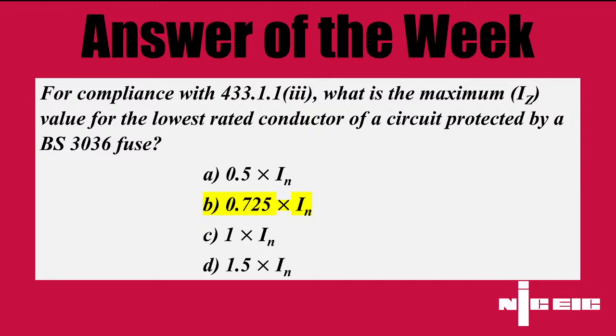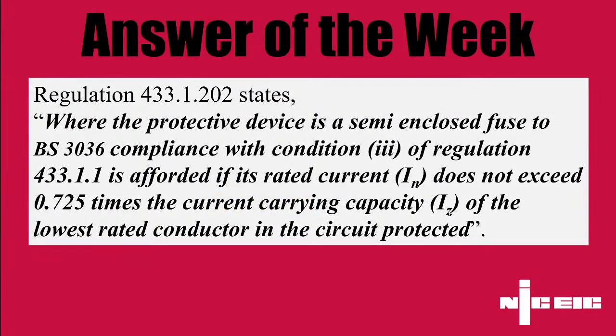If we go through a little bit of information as to why that is, within BS 7671 itself, firstly we'd be driven by Reg 433.1.202, which says where our protective device is a semi-enclosed fuse to BS 3036, then in order to meet indent 3 of regulation 433.1.1, it's afforded if the rated current does not exceed 0.725 times the current carrying capacity of the cable, Iz, of the lowest rated conductor in the circuit protected. So it is a little bit different. If you look in that section for current carrying capacity and overcurrent protection, quite often we look at that value of 1.45 times the rated value of our overcurrent protective device to make sure that the cables will be capable of carrying that current. So a little bit of background, very briefly.